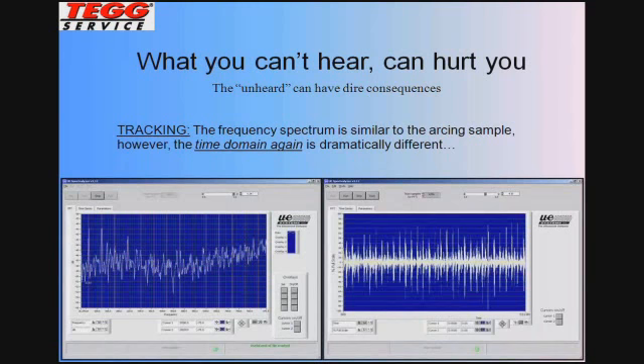If you look at tracking in the frequency and time domain, on the left-hand side here, it's very interesting because I like to say that arcing and tracking are almost twins in the frequency domain. And what I mean by twins is that the characteristic footprints are nearly identical. We have the first couple of fault frequencies on the harmonics, depending on which base frequency you're working with, and a lot of activity or frequency noise occurring in between those harmonics. If you were to use just the FFT tool, you could mistakenly call arcing tracking, or you could call tracking arcing. They're that similar based on our experiences. Where the major difference is in the time domain, which is why I believe you must use both these tools every time when you have a suspected problem.